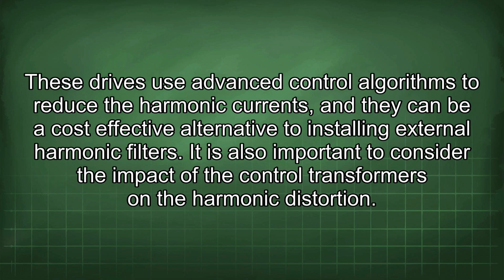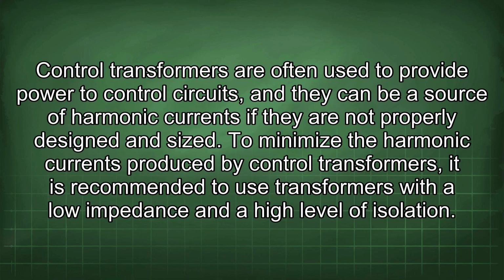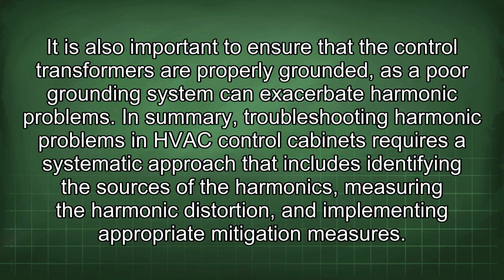It is also important to consider the impact of the control transformers on the harmonic distortion. Control transformers are often used to provide power to control circuits, and they can be a source of harmonic currents if they are not properly designed and sized. To minimize the harmonic currents produced by control transformers, it is recommended to use transformers with a low impedance and a high level of isolation. It is also important to ensure that the control transformers are properly grounded, as a poor grounding system can exacerbate harmonic problems.